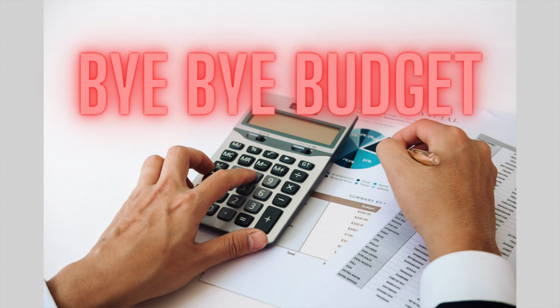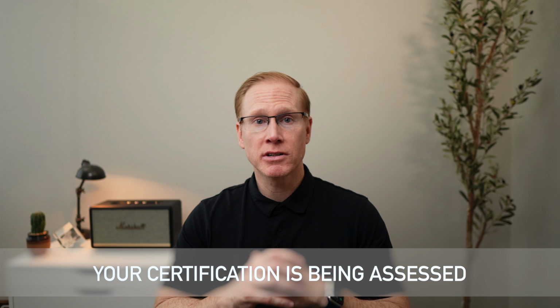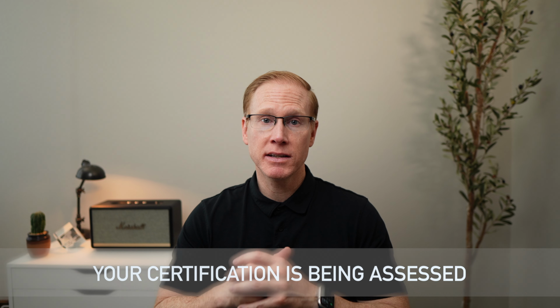Obviously, the potential for notified body supplier audits is a significant concern. You'll have to spend time preparing suppliers for the audits, then provide support when the audits actually happen, and your organization will need to pick up the expenses of your notified body, and often your supplier's costs, depending on how your quality agreement is structured. And another point to keep in mind is any nonconformances observed will be issued as findings against your organization. This is because, as the legal manufacturer, it is your certification that is being assessed.